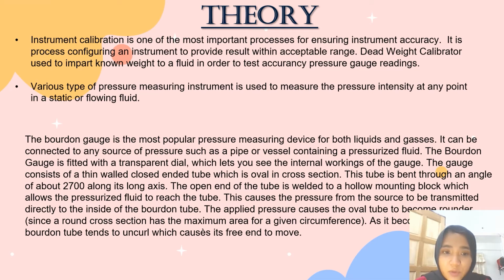The Bourdon gauge is fitted with a transparent dial which lets you see the internal workings of the gauge. The gauge consists of a thin-wall closed-ended tube which is oval in cross-section. This tube is bent through an angle of about 270 degrees along its axis. The open end of the tube is welded to a hollow mounting block which allows the pressurized fluid to reach the tube. This causes the pressure from the source to be transmitted directly to the inside of the Bourdon tube. The applied pressure causes the oval tube to become rounder, since a round cross-section has the maximum area for a given circumference. As it becomes rounder, the Bourdon tube tends to uncurve, which causes its free end to move.